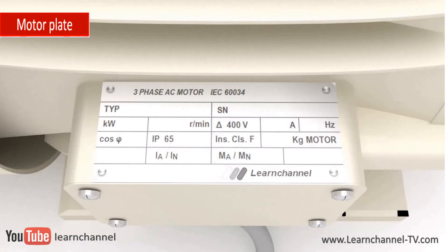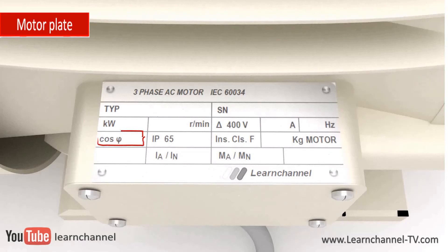To decide if this motor can be connected in delta or should be connected in star, you need the information about the rated motor voltage. In this case, the motor can be connected in delta within a 400-volt three-phase power supply. Because the motor coils are connected to AC, you need the information for the effective power factor. The rated input power, or electrical power, can now be determined by a simple equation.